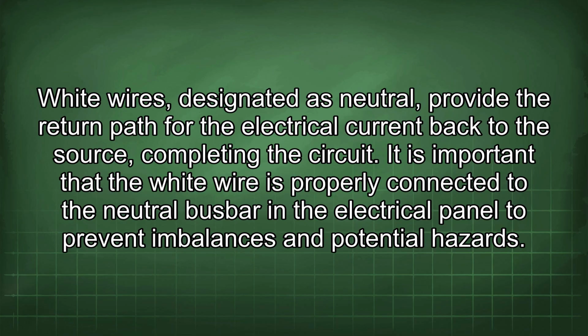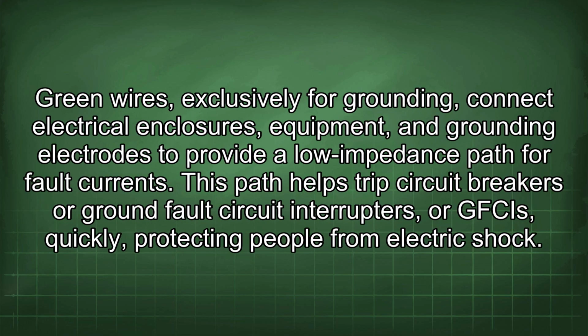White wires, designated as neutral, provide the return path for the electrical current back to the source, completing the circuit. It is important that the white wire is properly connected to the neutral busbar in the electrical panel to prevent imbalances and potential hazards. Green wires, exclusively for grounding, connect electrical enclosures, equipment, and grounding electrodes to provide a low impedance path for fault currents. This path helps trip circuit breakers or ground fault circuit interrupters, or GFCIs, quickly, protecting people from electric shock.